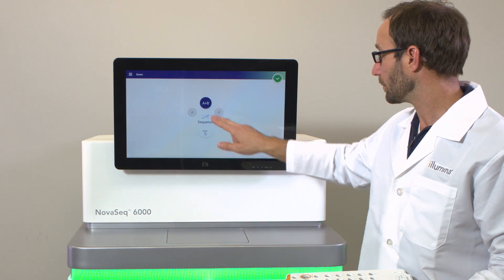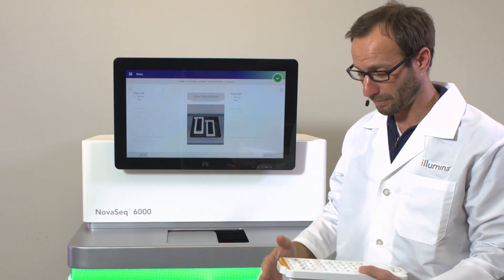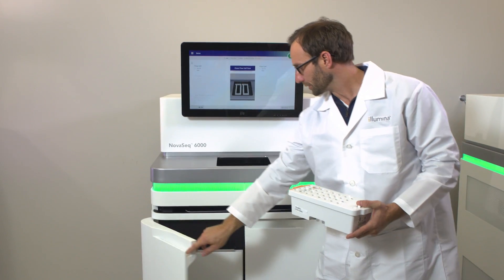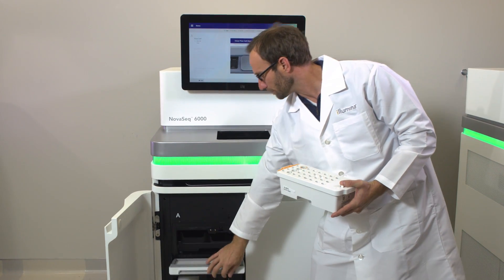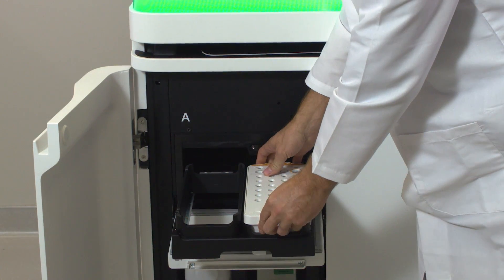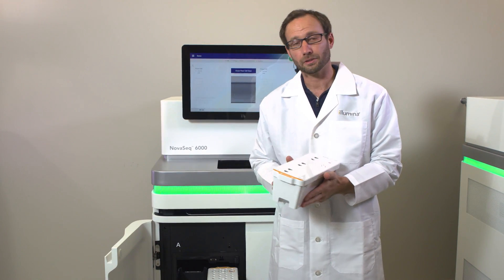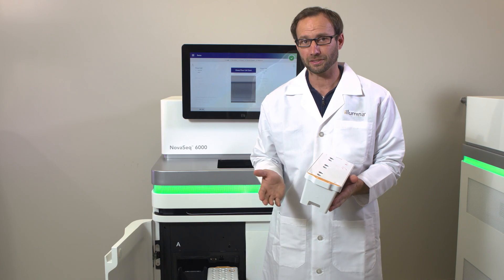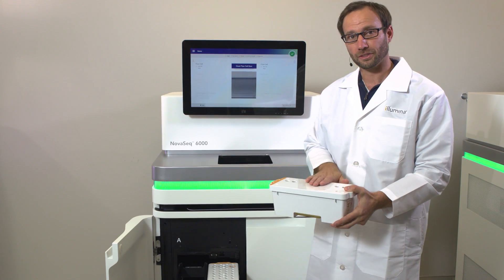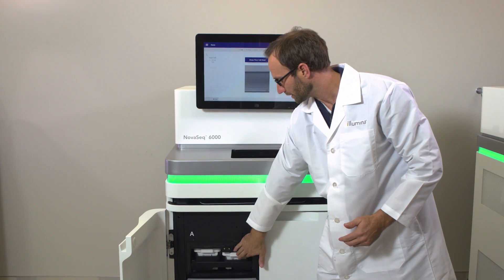To start, we're going to push the sequence button and then push OK. The flow cell door is going to open, and I've already loaded the library tube into the cartridge. My next step is to open the door, open the compartment for the reagents, and then slide the tray open. I'm then going to put the reagent cartridge into the tray. The second frozen cartridge is the SBS reagents. This cartridge is shipped on dry ice and stored at minus 20 degrees, and for thawing you can follow the same procedure as with your reagent cartridge. You don't have to load a sample in here, so you would just load this into the tray, close the tray, and then close the door.